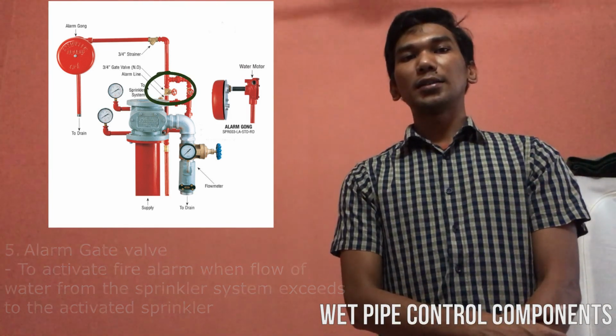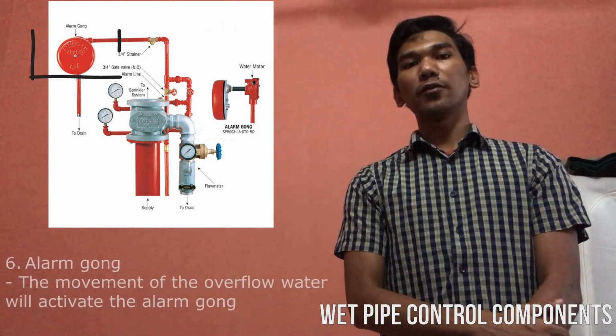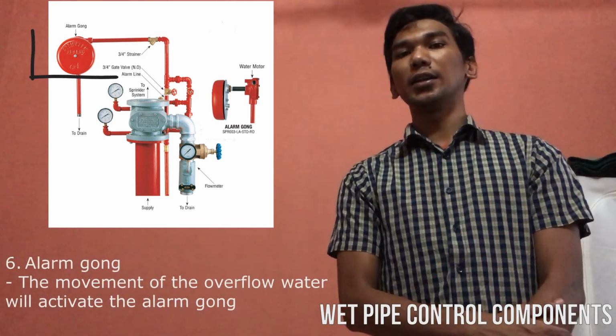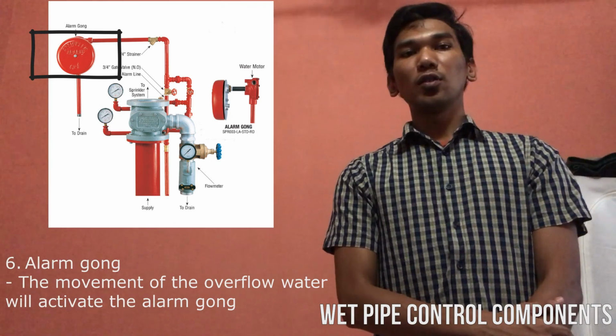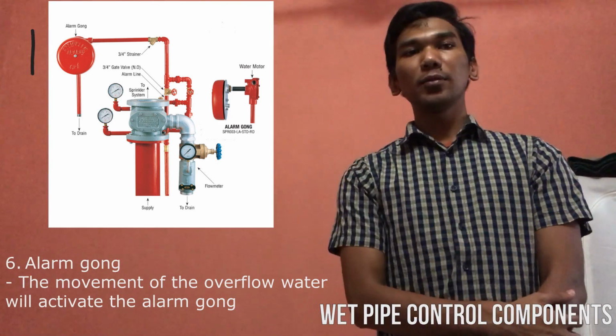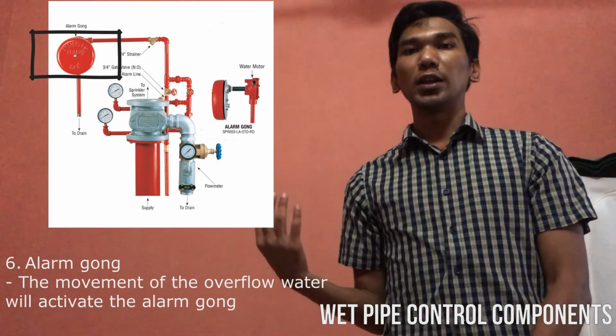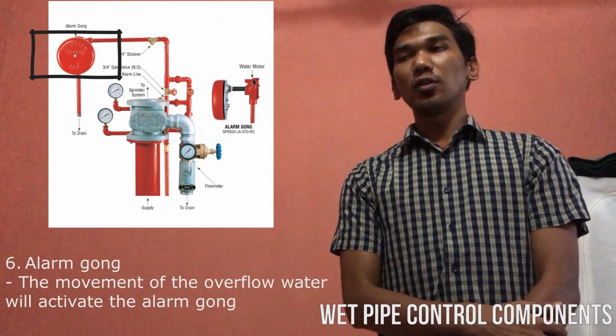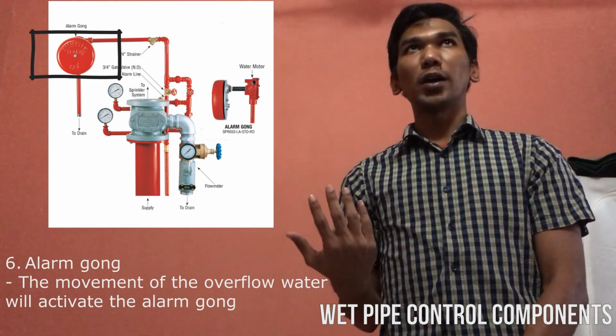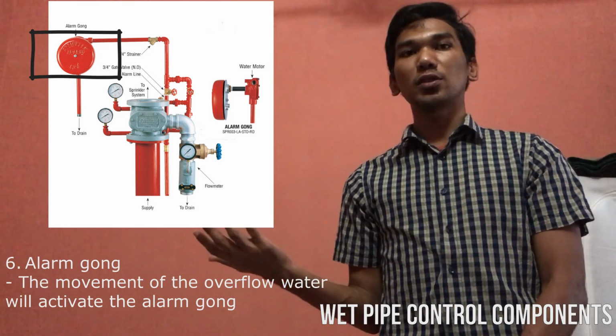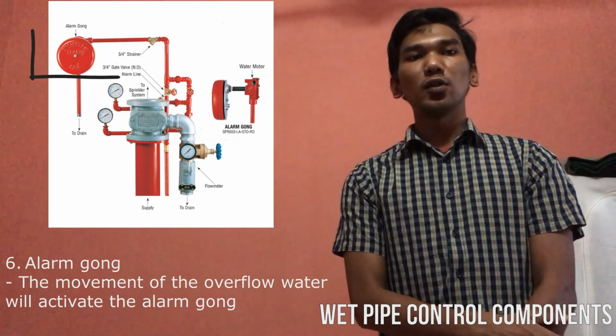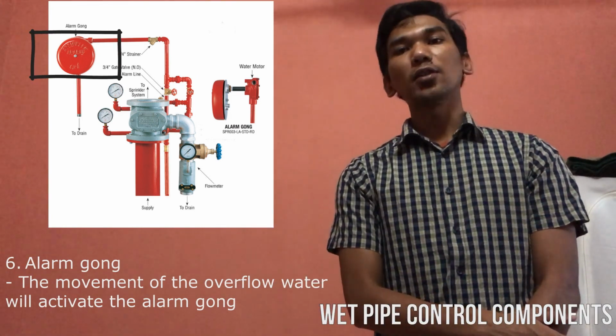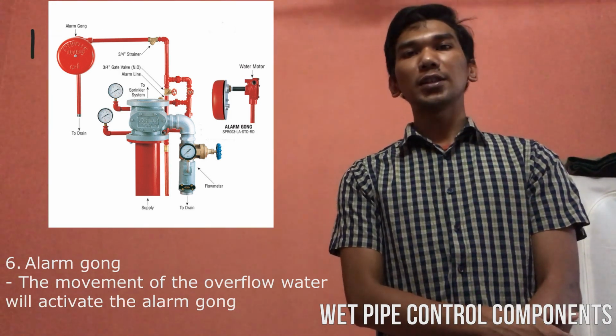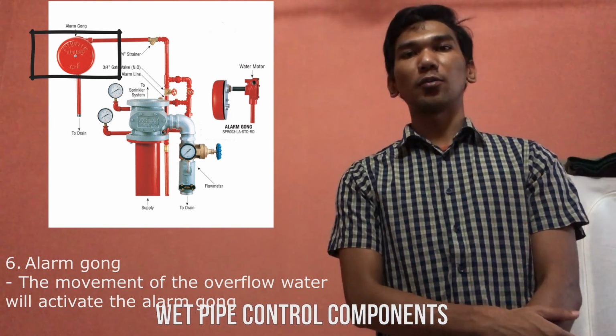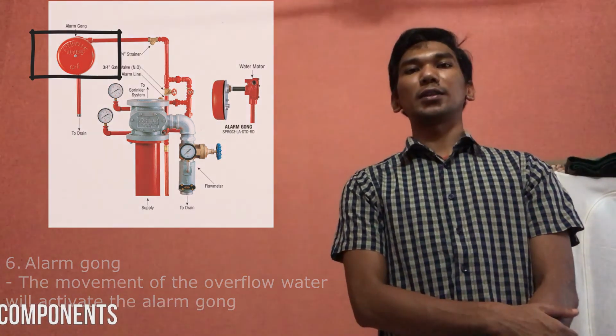So the last one is the alarm gong. The movement of the overflow water activates the alarm gong. As you can see from the diagram, the alarm gong is based on the water flow. There is only one more type of alarm gong, which is the electronic alarm gong. So that's all from me for the function and also the components of the wet pipe sprinkler system. Thank you.